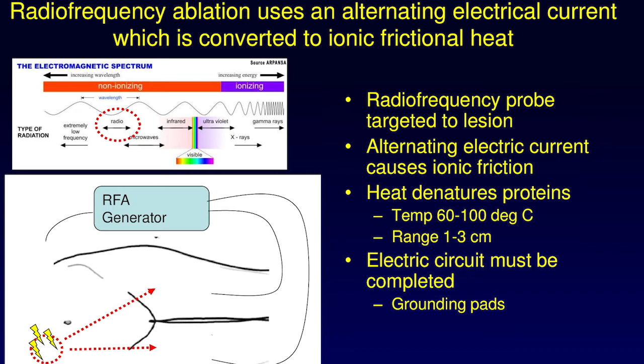Let's talk a little bit more about what radiofrequency ablation actually is. Radiofrequency energy is just a form of energy in the electromagnetic spectrum. It's just like light, but it's in a different part of the frequency spectrum. So how does this work? You have a patient and you insert the radiofrequency probe into the target lesion. There's a radiofrequency generator that creates this alternating current. That alternating current creates an electrical friction within the ions that heats up the tissue. The tip of this needle gets to about 60 to 100 degrees centigrade, and it can create heat at a distance of about 1 to 3 centimeters. This electrical circuit needs to be completed, so grounding pads are placed on the legs, and then that connects back up to the generator, and that completes the circuit.